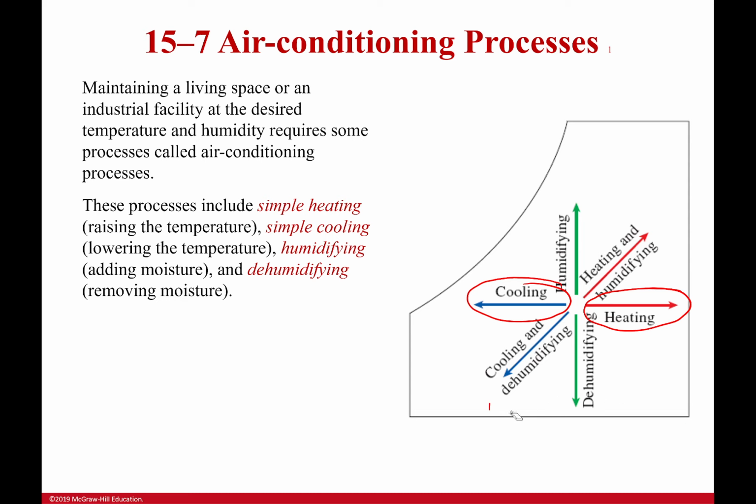Now, when I do that, we're going to find out through future slides that even though I'm heating or cooling, I'm not changing the amount of water that's in the air. The amount of water in the air is staying constant for this entire time. And so your specific humidity, not your relative humidity, is staying constant. The issue is that your relative humidity is changing. So as I cool, if I don't dehumidify, the air starts feeling really wet. Why? Because the relative humidity is increasing. It's getting to the point where eventually it's just going to precipitate out.